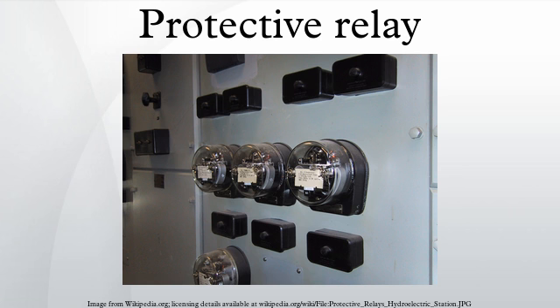Differential protection requires a set of current transformers at each end of the power line, or each side of the transformer. The protection relay then compares the currents and calculates the difference between the two. As an example, a power line from one substation to another will have a current differential relay at both substations which communicate with each other. In a healthy condition, the relay at substation A may read 500 amps and substation B will read 500 amps. If a path to earth or ground develops, there will be a surge of current.